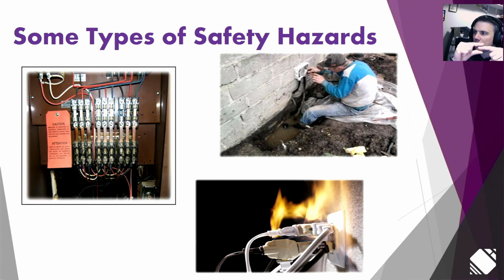I'm not sure how much you can see that - yeah, it's showing up. So as it's in there, there's a little bit of a gap between the lug and the copper wire, and it would arc in between them, which in normal use, a little small arc like that, no big deal. But over time, that arc creates localized heating, burns a spot in the copper wire, and every time it's arcing, it's producing more and more heat. You can actually start a fire from that, and if nobody's home, or even if you are home, you don't notice it because it's in your basement, put away in your mechanical room - nobody's down there looking for fire and looking around.